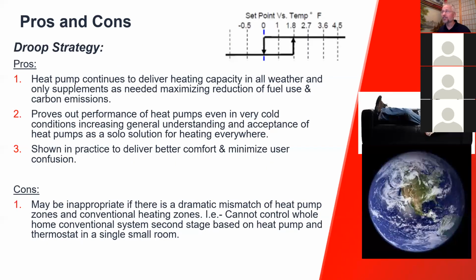Okay, the droop strategy is, as I described, you can see in this little figure up here. You're at set point when it's at 0, and if the temperature drops a couple of degrees below set point for some period of time, 10-15 minutes depending on the settings of the system typically, it'll kick on the backup heating system, which brings the temperature up to the set point and shuts off, and allows the heat pump to resume within whatever range. And if the heat pump ever needs help again, it'll call back.